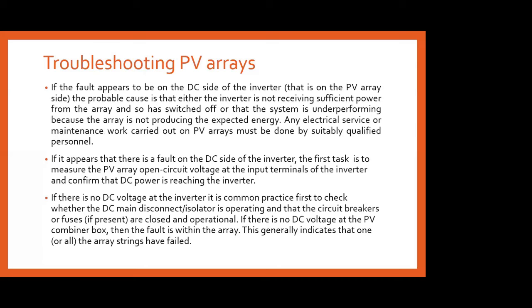Of course, your PV array comes under the DC side of the inverter, that is, the connection before the inverters. From the PV arrays up to the inverter, we know that is completely the DC side, and those things have to be checked. This process varies depending upon the configuration of the system. Here we are assuming that there is a PV combiner box between the array and the DC main, nothing but your DC disconnector or an isolator. In this example, we are considering that there is a PV combiner box present.